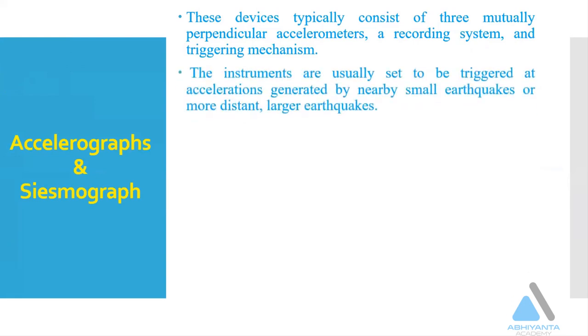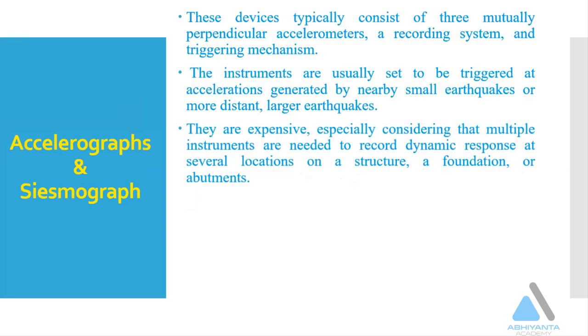So let's understand about the accelerograph and seismograph. The device typically consists of three mutually perpendicular accelerometers, a recording system, and a triggering mechanism. The instruments are usually set to be triggered at accelerations generated by nearby small earthquakes or more distant larger earthquakes. They are expensive, especially considering that multiple instruments are needed to record dynamic response at several locations.